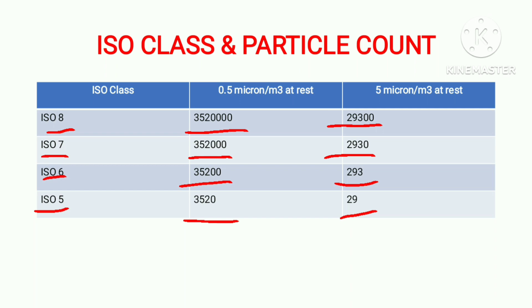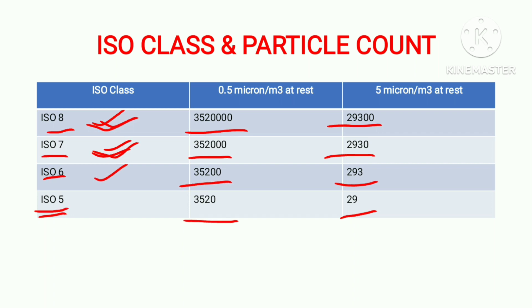In the pharma industry, mostly three ISO classes are used: ISO 8, ISO 7, and ISO 6. ISO 5 is mostly not used in pharma. ISO 8 is used in general production areas like granulation, blending, and QC. ISO 7 is used in microbiology and sterile areas, and some companies also use ISO 6 in microbiology and sterile areas instead of ISO 7.